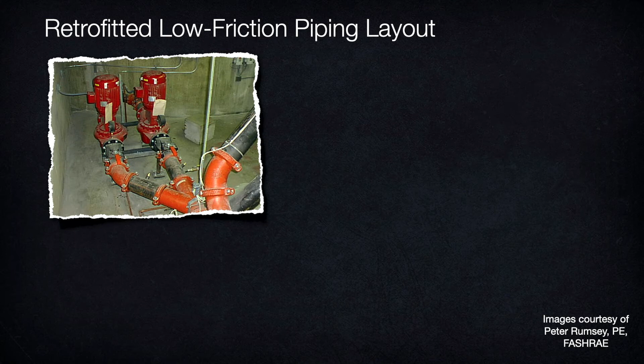You notice the Y joint instead of right-angle bends — a sweep bend and then a diagonal through the air, fat pipes, no right angles. Then he repiped another pumping loop and added variable frequency drives, and together those doubled the flow and saved 85% of the energy.